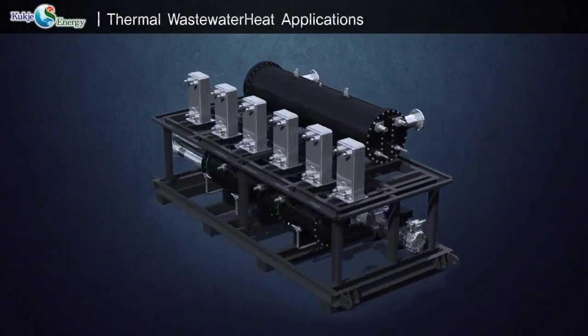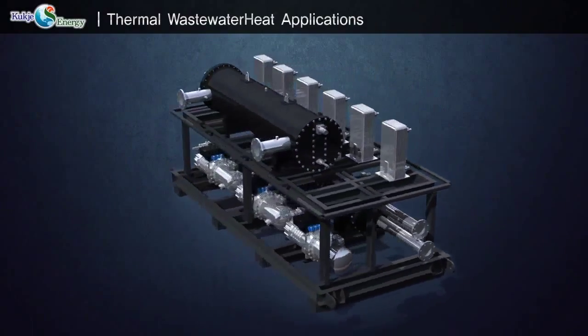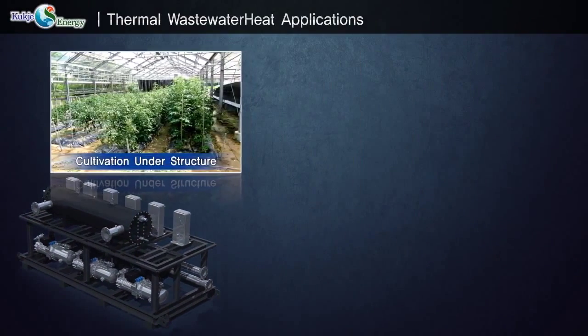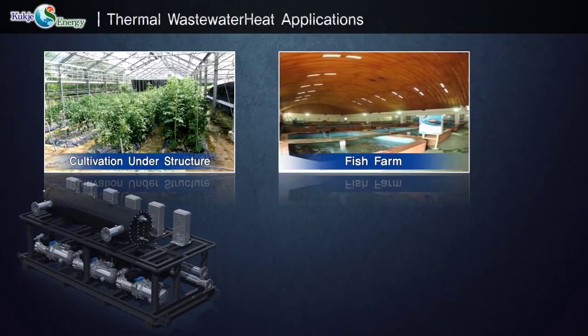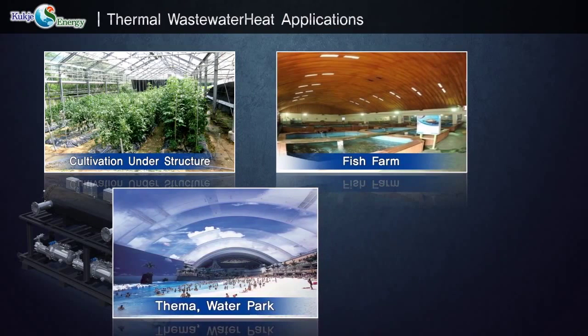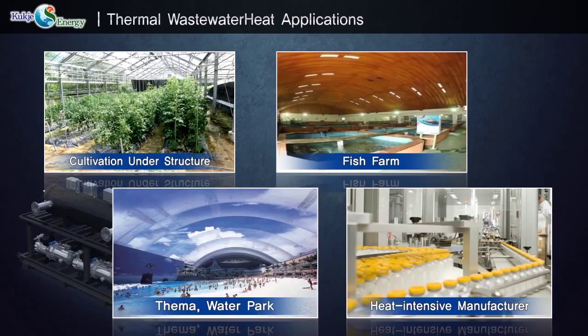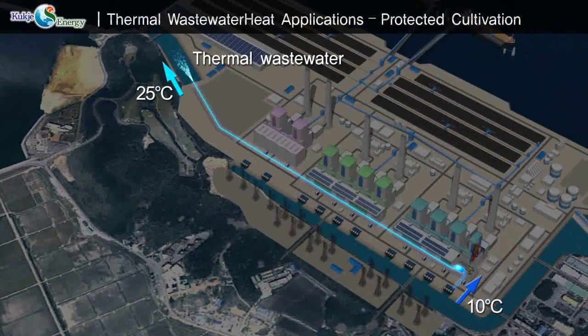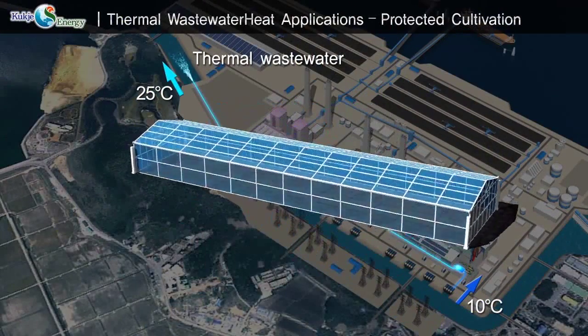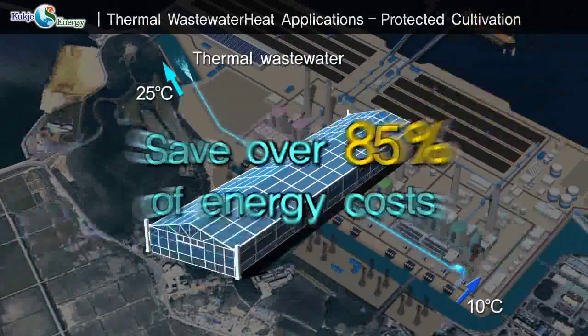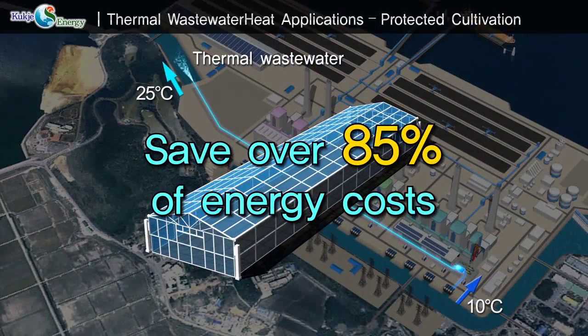Heat from the thermal wastewater can be utilized in protected cultivation complexes, heat-intensive manufacturing industries, water parks, and fish farms. Since it is capable of rapidly cooling down to -90 degrees Celsius, it can maximize energy savings by operating refrigerated and frozen warehouses simultaneously. When applied to protected cultivation complexes, it can save up to 85% of energy costs compared to conventional protected cultivation.